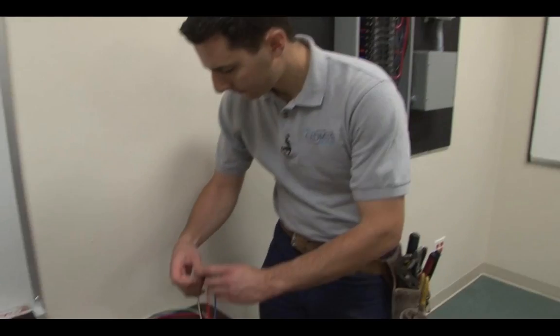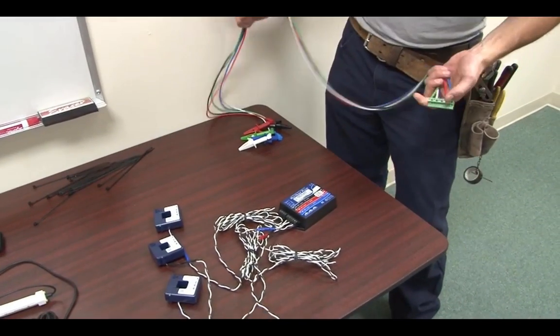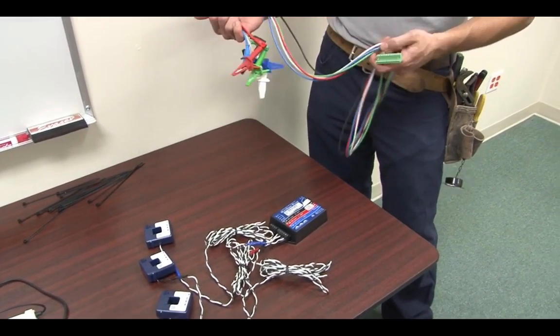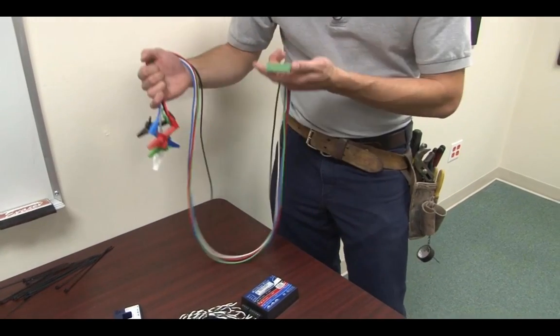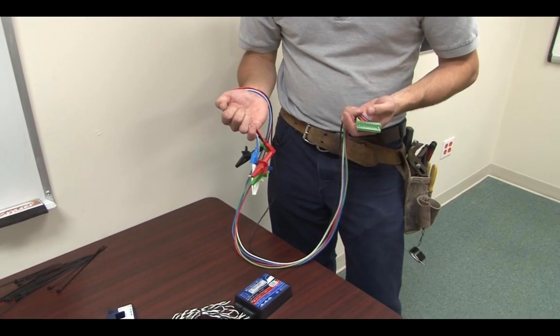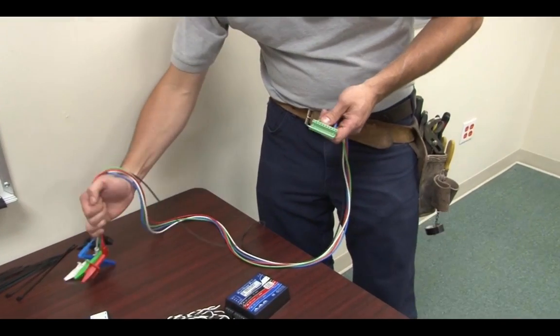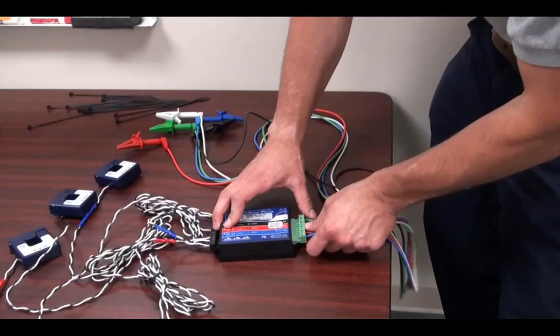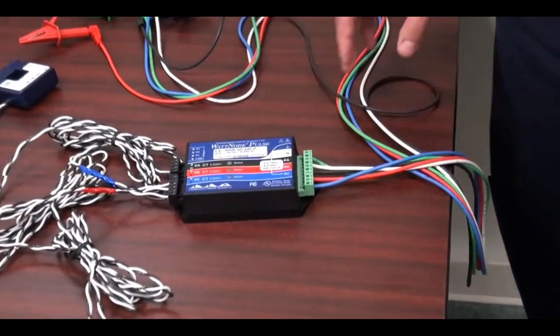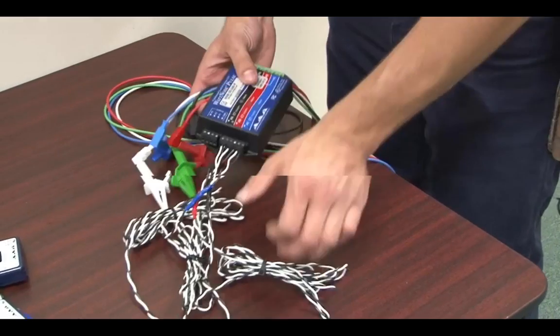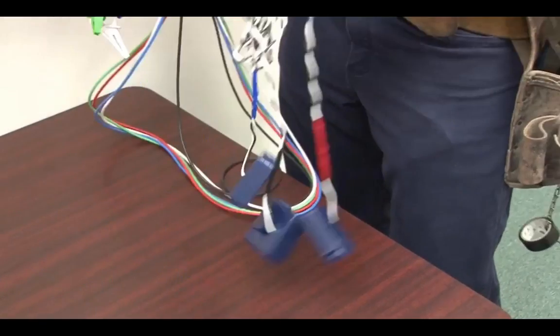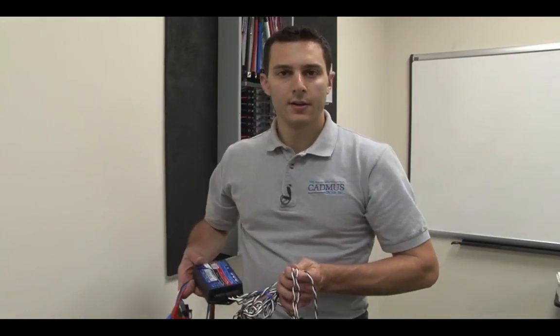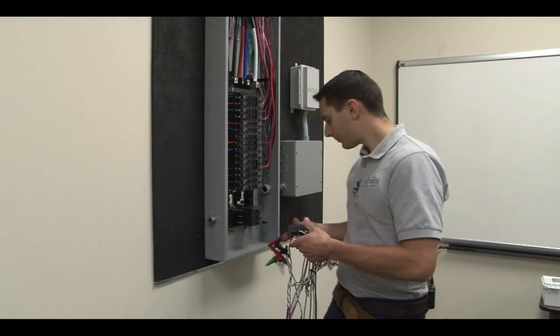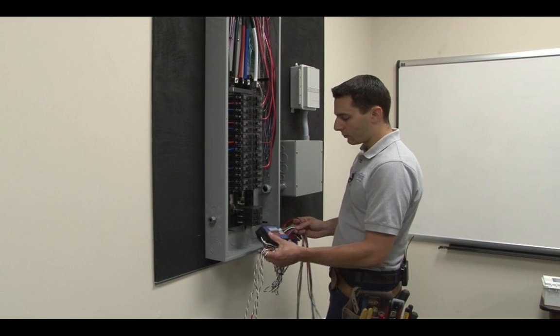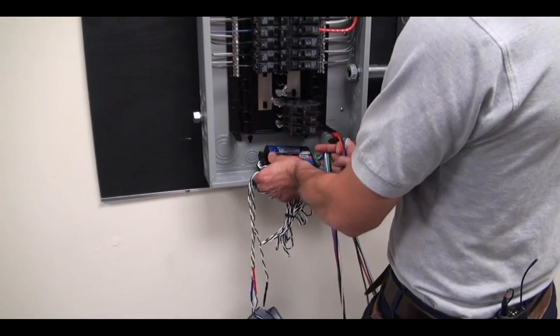We're now ready to plug our voltage leads into the Wattnode. For this, we'll use the Wattnode lead set available from Onset. This particular lead set is double insulated and rated for 1,000 volts. Now that our Wattnode is pre-wired, it's ready to install. We'll place the Wattnode in the location where we've determined.